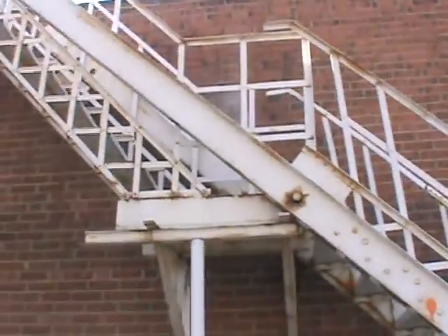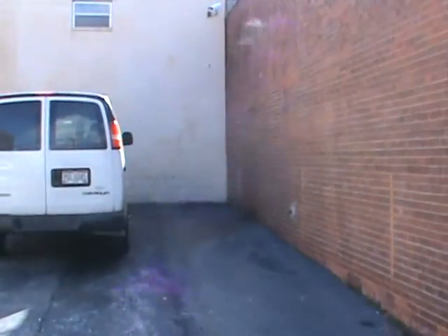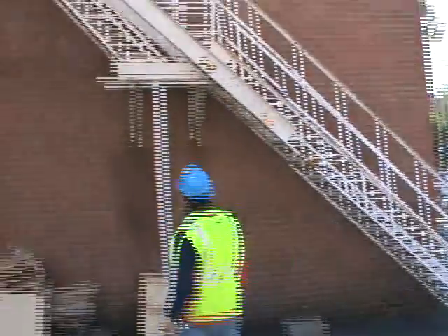And if they have to egress people up from above, there are a couple of options. Do emergency repairs on this to make it functional until such time that permanent repairs take effect, or immediately go into permanent repairs to get this thing certified in lieu of a load test. Another option is you can mothball this, and you can probably put some scaffolding in that corner, so you rent it by the month. Temporary OSHA approved scaffolding up to the top basically feeds the people up above and the people from the other location. So the OSHA approved scaffolding will make this site still functional until such time that repairs are done. So you can mothball this till the repairs are done.